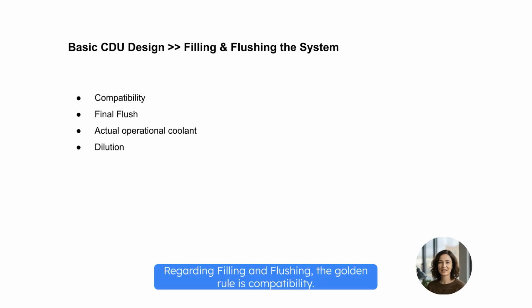Regarding filling and flushing, the golden rule is compatibility. Never introduce a cleaning agent that conflicts with your loop chemistry. Always consult the vendor first. But here's the critical protocol. Regardless of what you clean with, the final flush must be done using the actual operational coolant. This is mandatory to prevent dilution before you go live. Use a dedicated flushing cart to control this process.